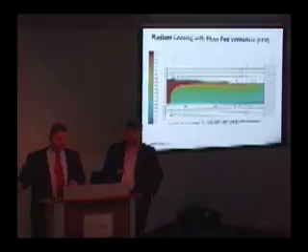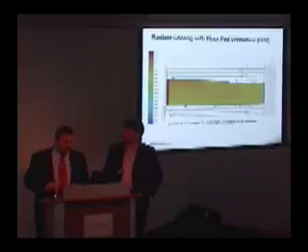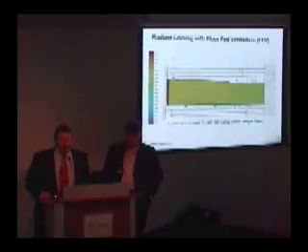We now have many variables we didn't have before: the temperature of the ceiling panel, the chilled water flow rate through it, the volume of air coming from underneath the floor, and the ability to modulate how much air goes through the double wall. We need to find the right balance. This graph shows operative temperature, which is now considered a much better means of measuring human comfort in a space.